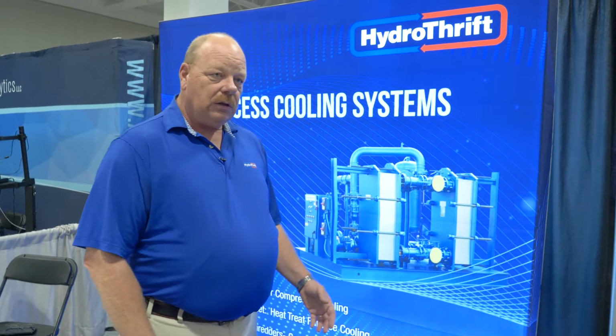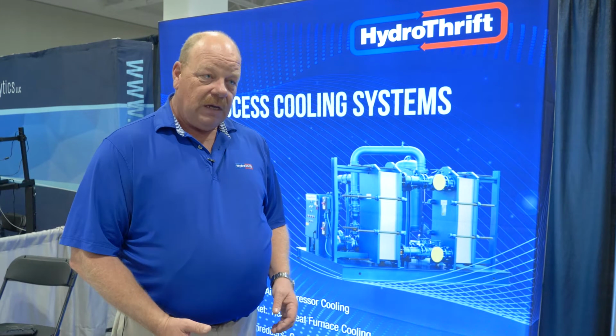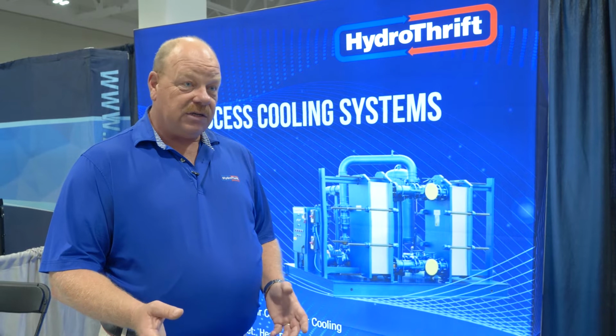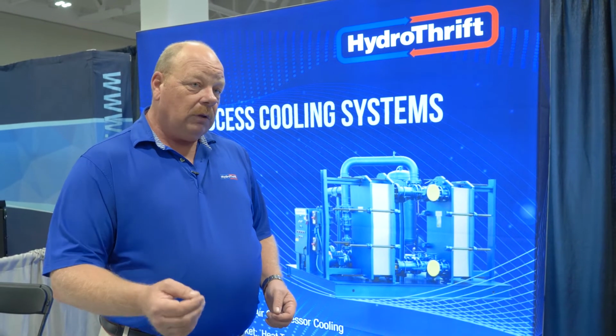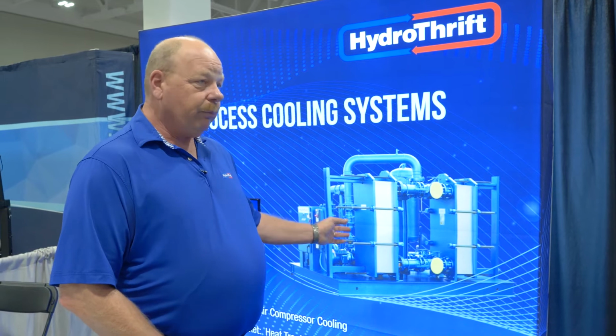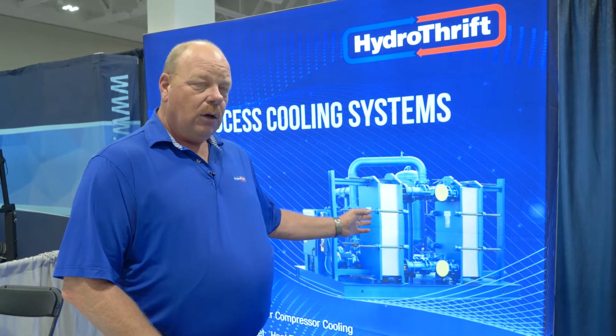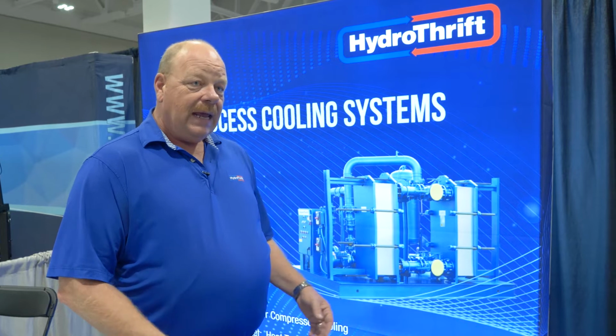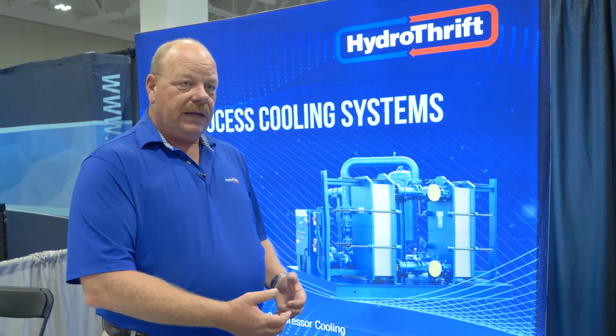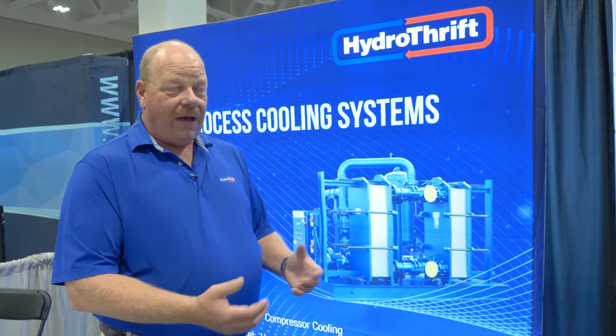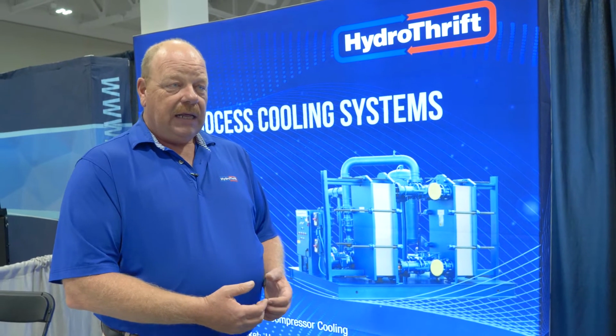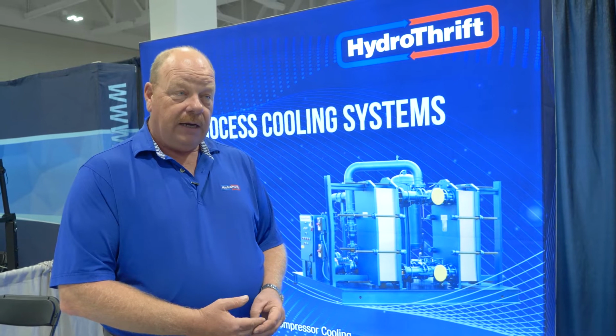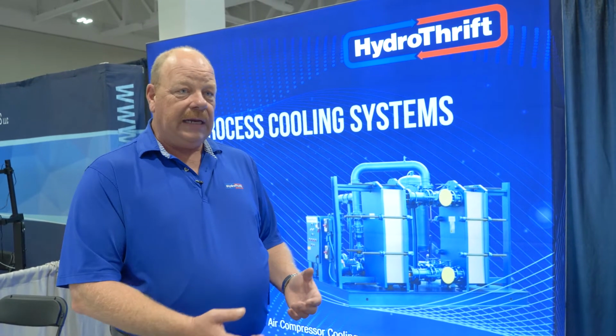So many times large companies have water-cooled air compressors, and they use open tower water to do the cooling on the air compressors. The problem with that is that the water in open towers is very mineral laden and can sometimes be quite dirty. When that mineral laden water hits the air compressor cooling surfaces, which are sometimes around 300 degrees, any mineral content in that water will plate out as what's called lime or scale. And it will foul those heat exchangers to the point that the compressor will start overheating. And it'll have to be rebuilt and cleaned and everything.